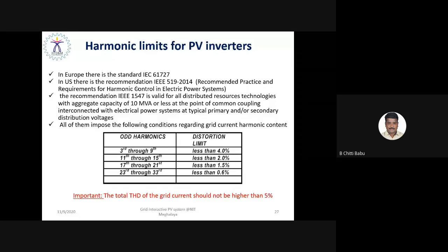So whatever standard you follow for a grid integrated solar PV system, the limits imposed by the standard have to be satisfied. The total harmonic distortion of the grid current should always be less than 5%. For the individual harmonic orders, the distortion limit is a maximum of 4% for the 3rd through 9th order, and it should be less than 0.6% for the frequency orders from 23rd till 33rd. And even now, I can see in the recent literature that harmonic presence in the converter above the 33rd harmonic, what is called a supraharmonic, can still cause EMI or EMC problems associated with the magnetics in the power converter. That still has to be investigated further.